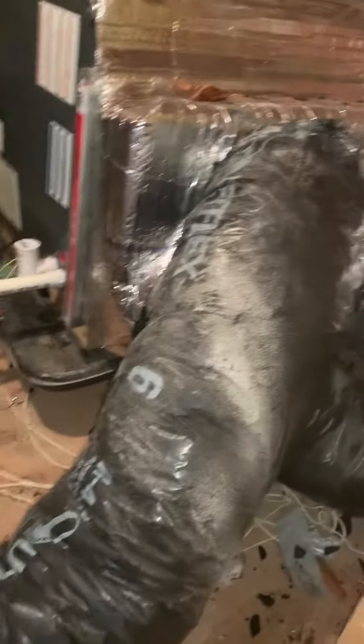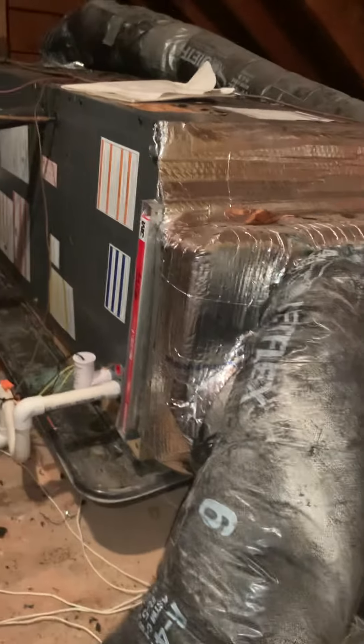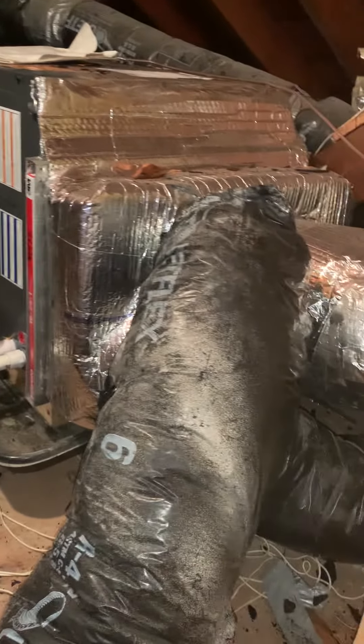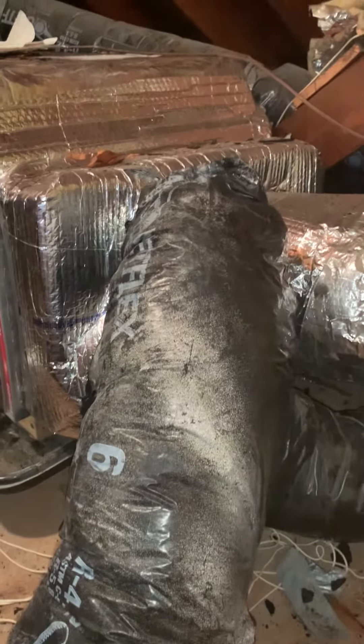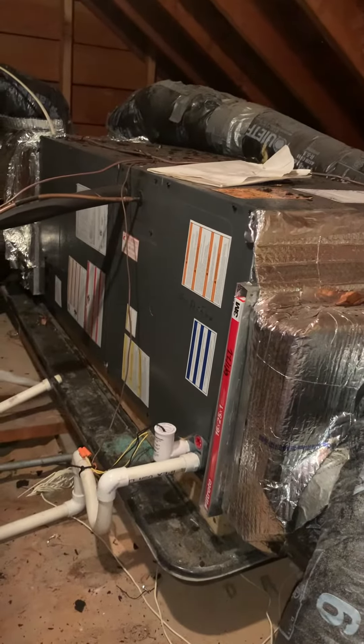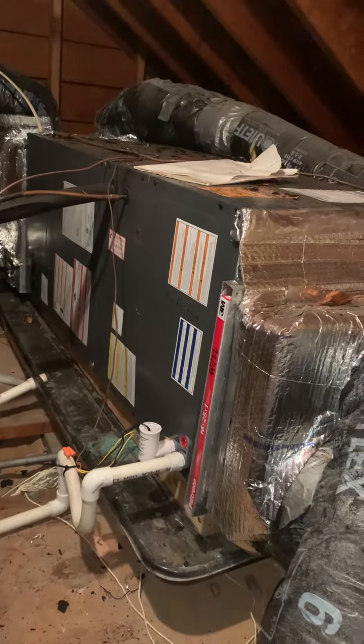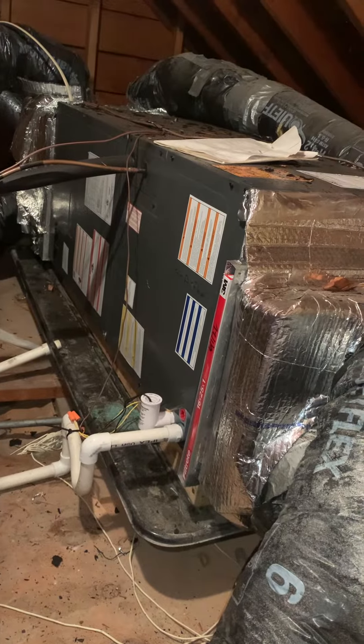Taking a look at the second floor system. Speaking with the homeowner, she's had a few issues over the years. I see quite a few things with the installation process that are causing issues too. When we're pulling heat in from the return, supply runs are pinched off. Looking at redoing that — this unit could definitely be moved closer to the wall.